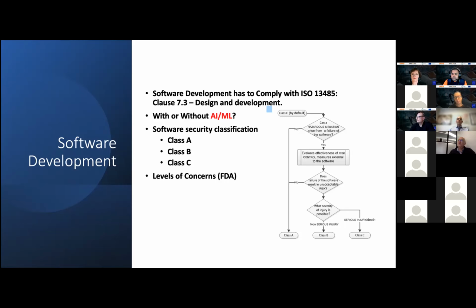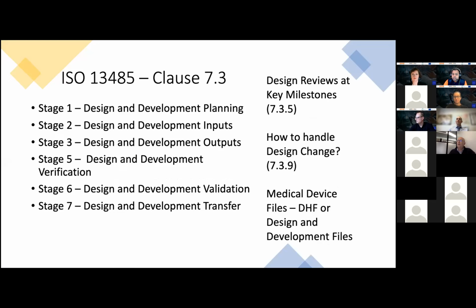By default, software starts off as class C, and then you work your way through this very simple flowchart to come out with a software safety classification. If it can't cause a hazardous situation arising from the failure of the software, then it's a class A. If it evaluates the effectiveness of risk control measures, it can be either class B or class C. Class C if it causes a really severe injury to a patient. So there's an intermediate one, which is medium risk, a high risk one, where you cause serious injury to patients, and no risk to patients. The reason why that's important is it then reflects into the documentation that we're going to need later on.